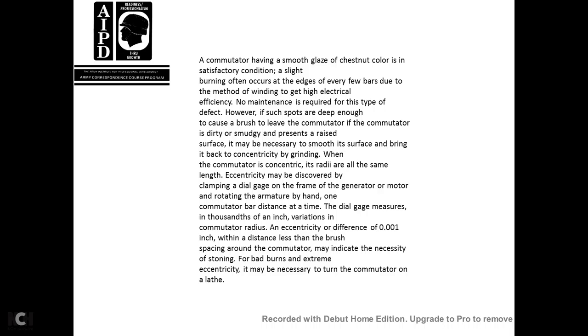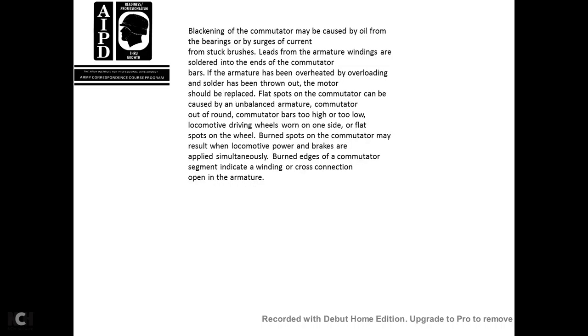The dial gauge measures the thousandth of an inch variation. Commutator eccentricity at 1/1000th of an inch in a distance less than the brush spacing around the commutator may indicate the necessity of stoning for the bad burns. Extreme eccentricity may make it necessary to turn the commutator on a lathe.